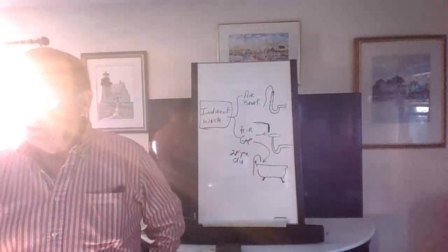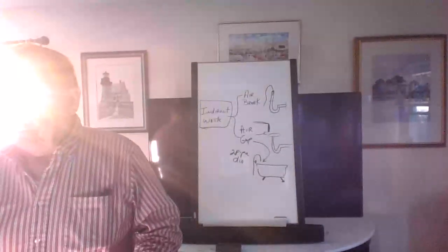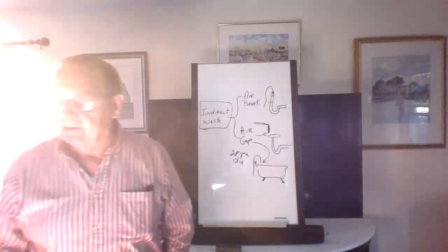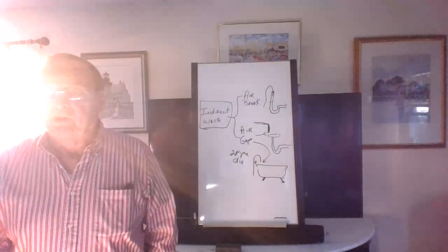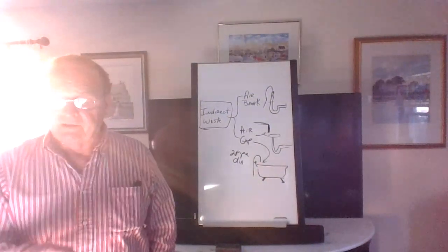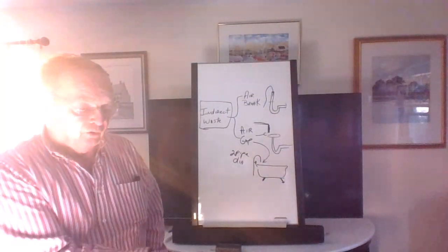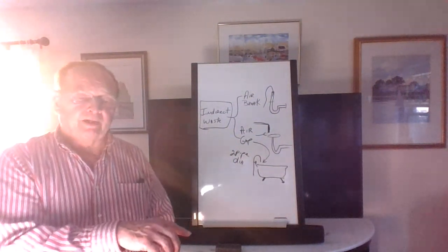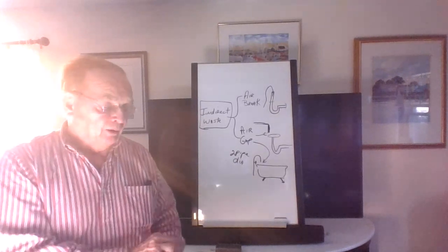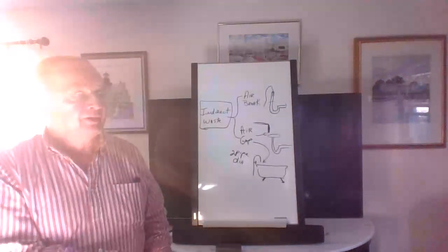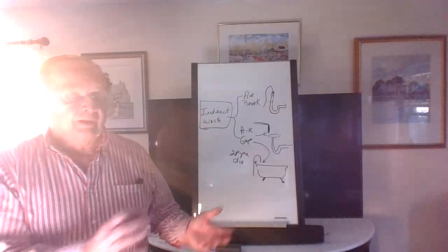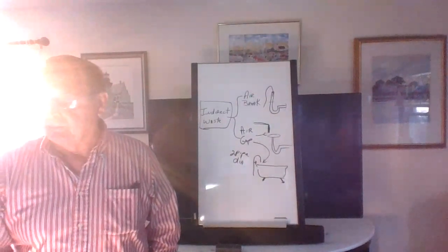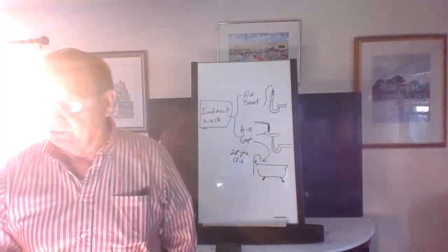And the boiler blow off, I don't even know why this is here. This is not plumbing. This would be like on a steam boiler. You would have a spring-loaded valve. Some of you guys that have seen steam boilers know there's a spring-loaded valve. You turn it, and it's facing straight down, and usually there's a bucket there. Maybe a little short piece of pipe, maybe not. You open it, and it blows down all this rusty, nasty-looking stuff. And you're supposed to do that like there'll be a little tag there like every month, which of course never happens. I don't know why it's here because that boiler is not part of the plumbing, but it's here. So we'll talk about it.